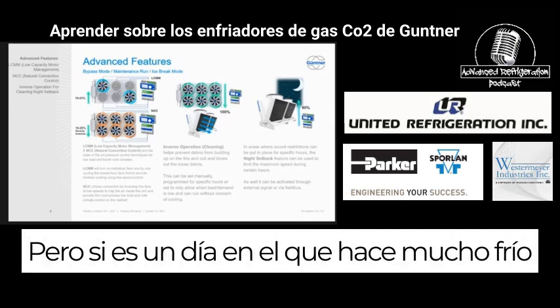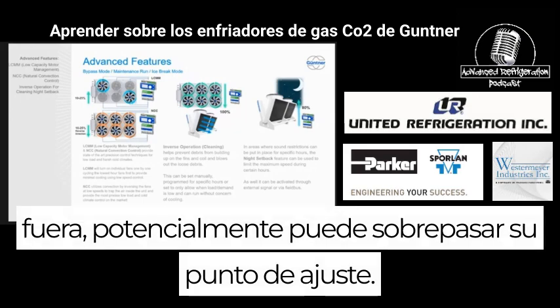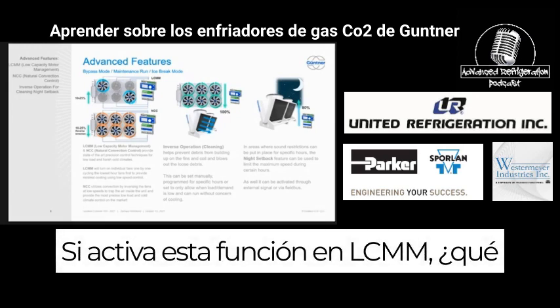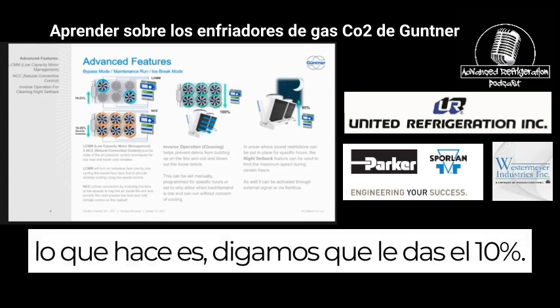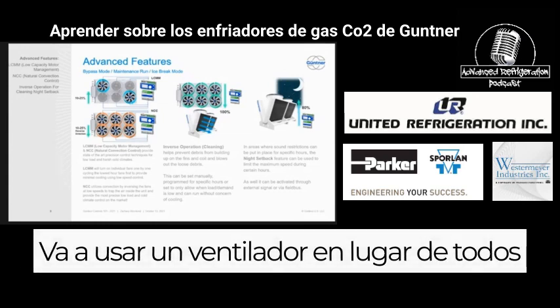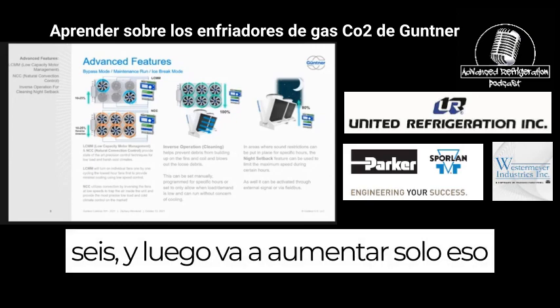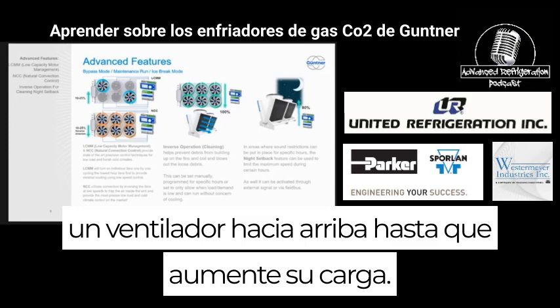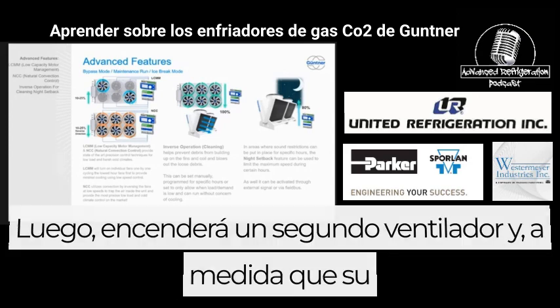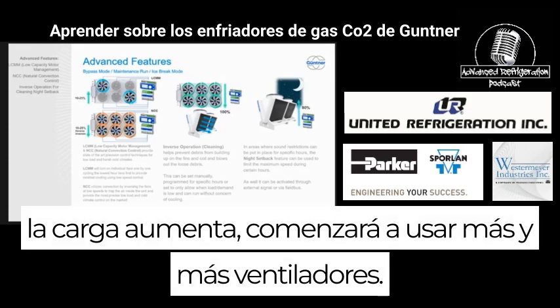But if it's a day where it's super cold out, you can potentially overshoot your set point. If you turn this feature on, LCMM, what that does is, let's say you give it 10%, it's going to use one fan instead of all 6. And then it's going to ramp just that one fan up until your load increases. Then it'll kick on a second fan. And as your load increases, it'll start using more and more fans.